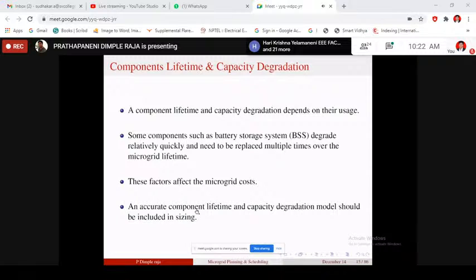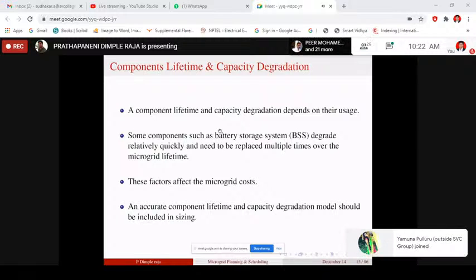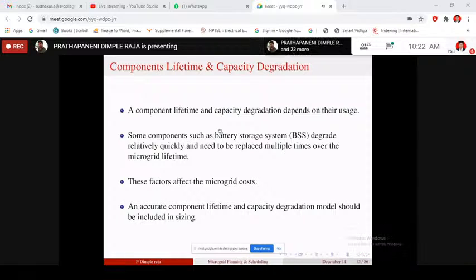So I will briefly tell you what we need to consider while designing, planning, or sizing a microgrid. First, we have to implement the optimal power dispatch strategy, whichever reduces the microgrid operational cost. Second, we need to take care of uncertainties. Third, if possible, implement demand side management into the sizing algorithm, which can reduce component sizes. Fourth, we have to include component lifetime and capacity degradation.